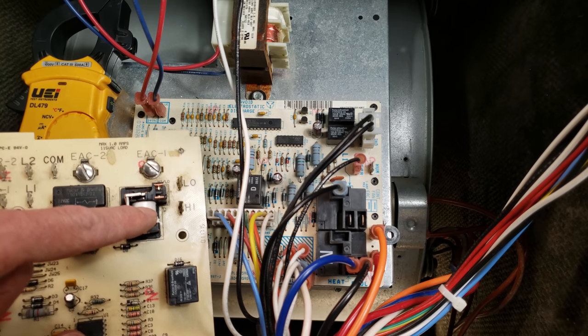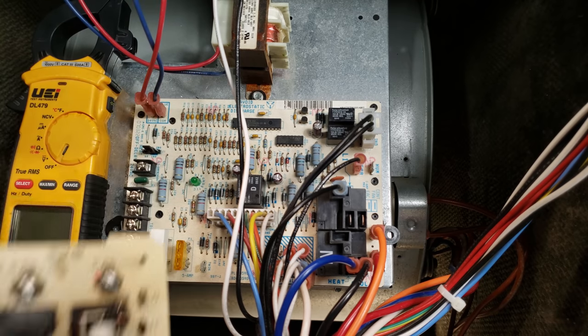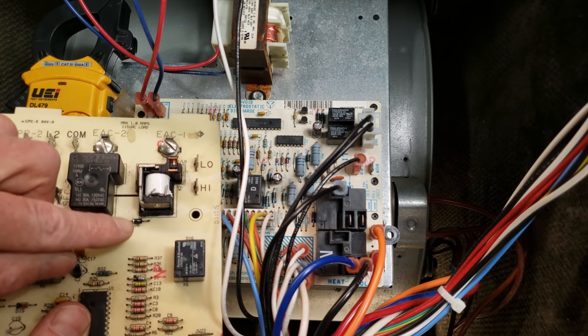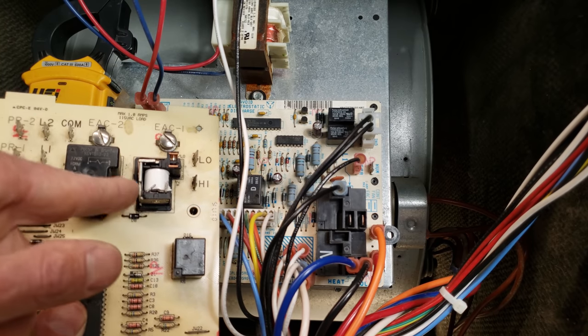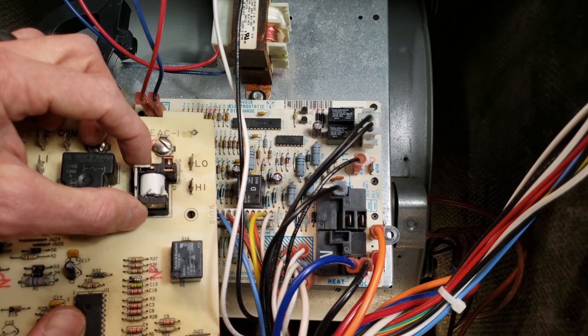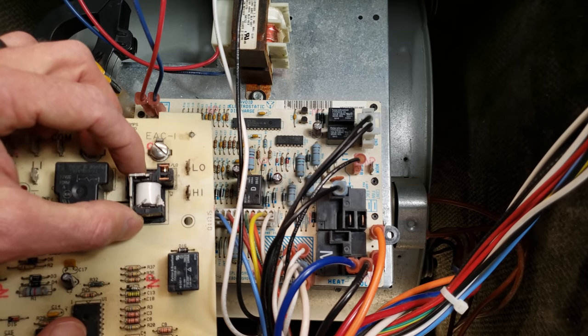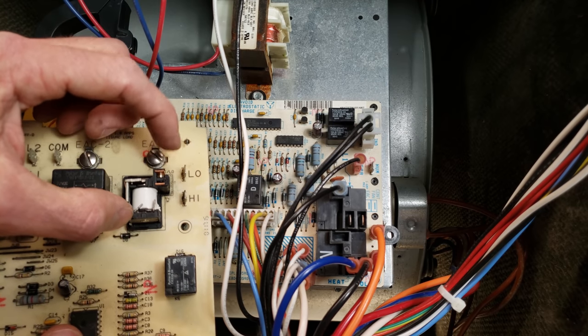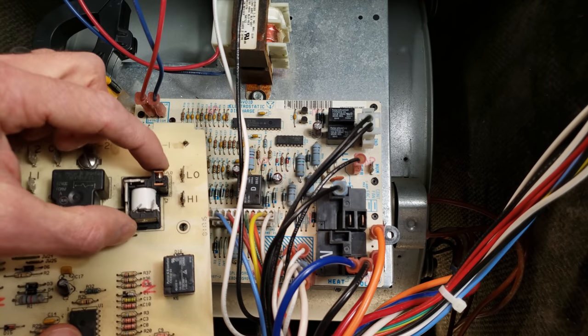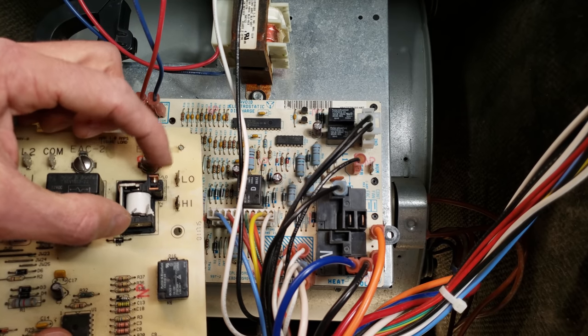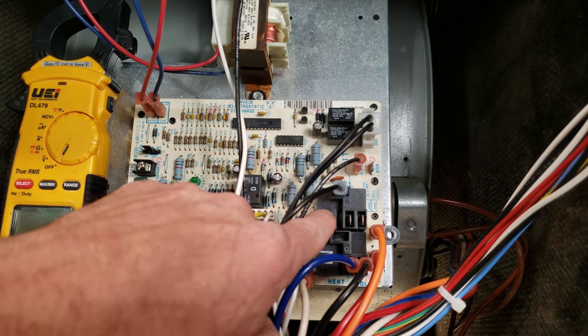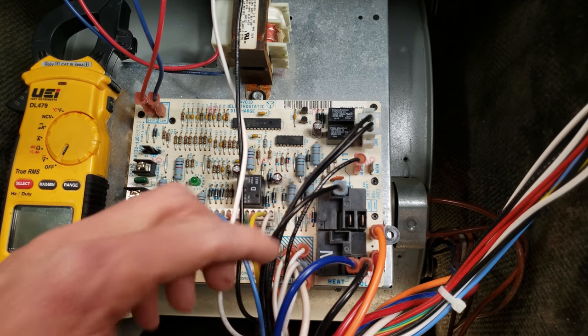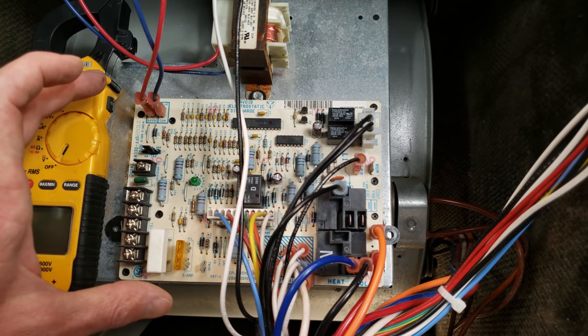You're going to supply direct current to this coil through the board, and you have a contact on the back of this control board connected to this piece of metal. See how it moves back and forth? It's normally closed between here and here, and when you power this coil it's going to suck this down, and now the contact between here and here are going to be open. Both of these relays are used anytime you're telling the control board to turn the blower on.